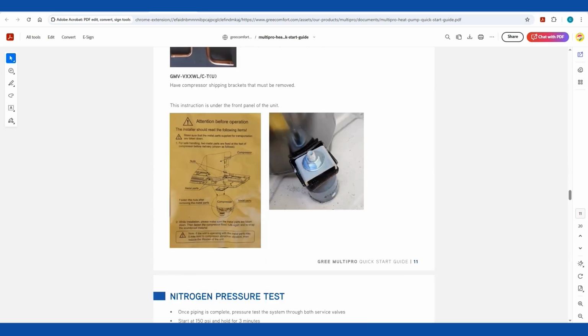Another thing I want to point out real quick, on the Ultra machines, make sure we've removed these shipping brackets for the compressor. There's 2 of them on there. They give you this big attention notice there. Hopefully you've seen it. So before you commission this unit, go in there and take these metal brackets off and put the nut back on there. Get rid of those.